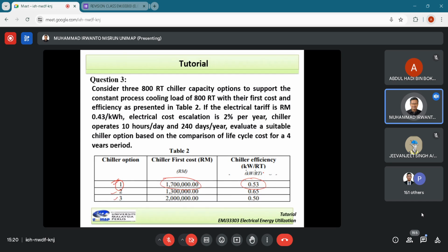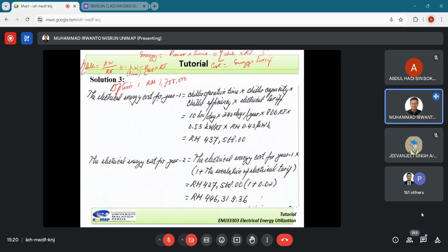Okay, now we find this: in the first year, chiller operation time, and then power equals chiller efficiency multiplied by chiller capacity. It is in RT, efficiency in kilowatt per RT. We can break this down, multiply by electric tariff because this is cost.